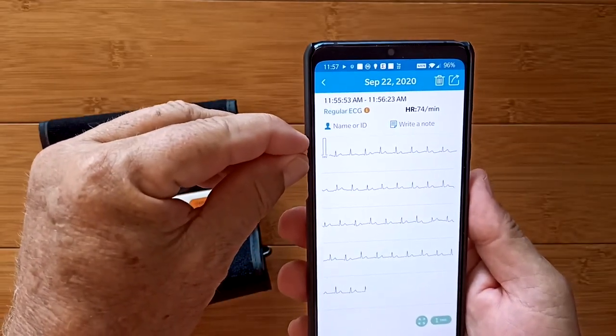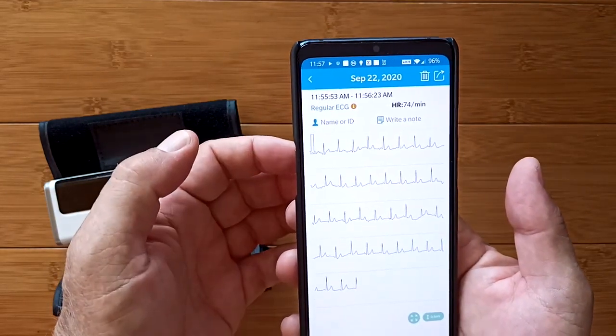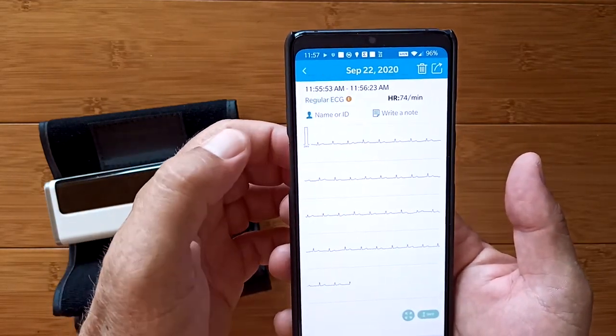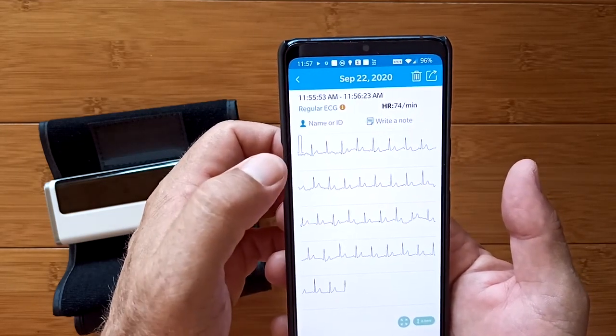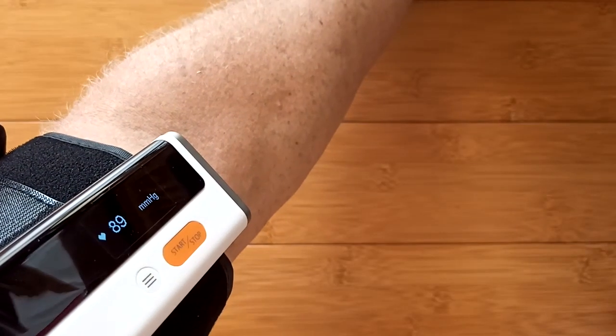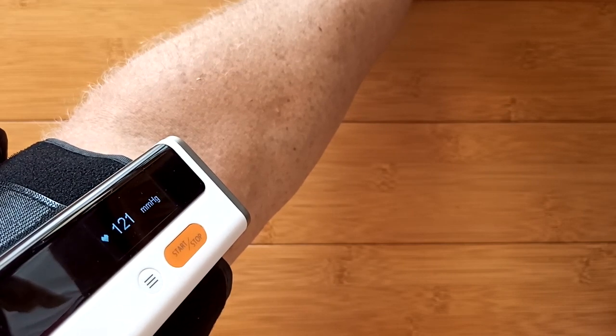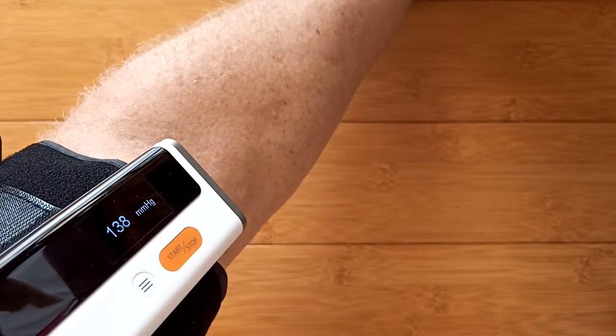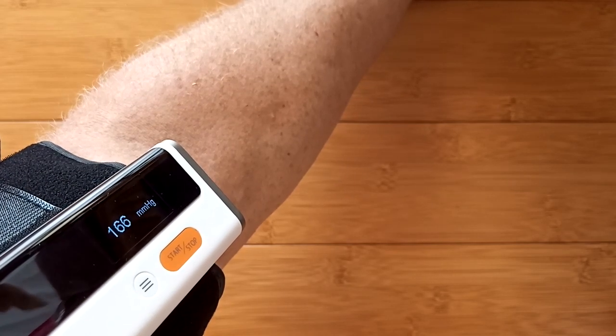It gives you your heart rate at the beginning and the overall chart. I touch it and I can make it bigger; touch again, really small. It has three different ranges of display. I can tap here and make it really large. It should pump up to about 200, maybe a little lower. I hear the motor going — it's getting tight.